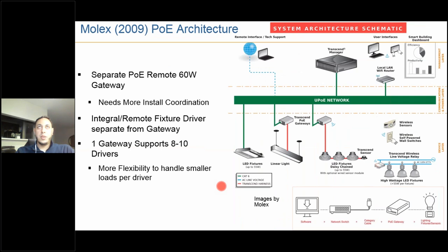Start with Molex, which became a PoE company in 2009. A little bit to note about their system architecture: they have a remote gateway. The way they work is they have their PSE devices, their power sourcing equipment devices, connected via PoE cable to what they call their gateway. In the Molex system, it's called the Transcend Gateway, and each gateway can support about 8 to 10 drivers, depending on the power requirements and size. So it's a bit of a distributed architecture where each gateway connected to a switch's port can connect a couple of fixtures and drivers.